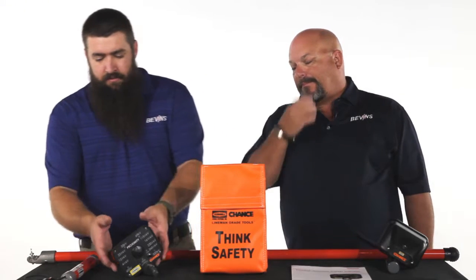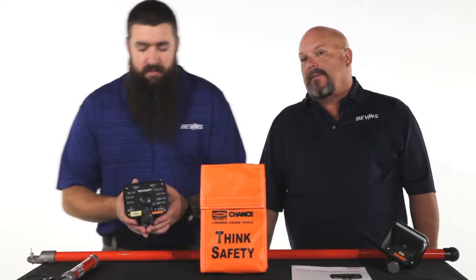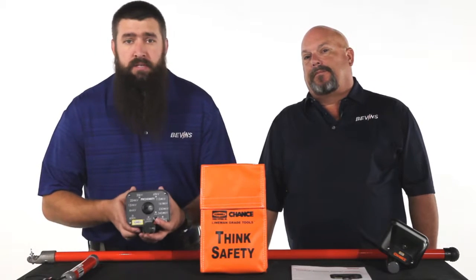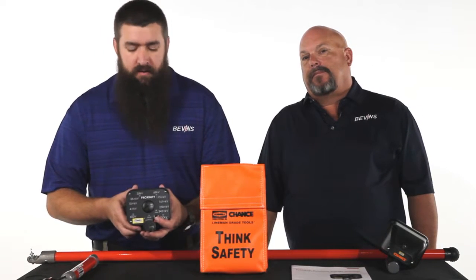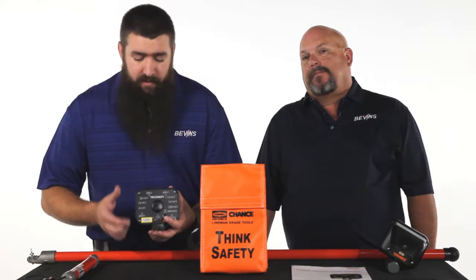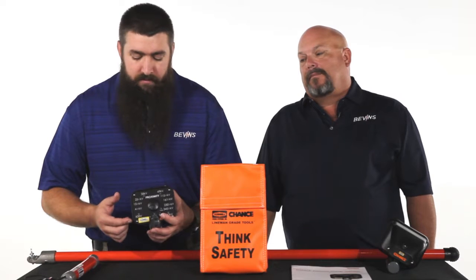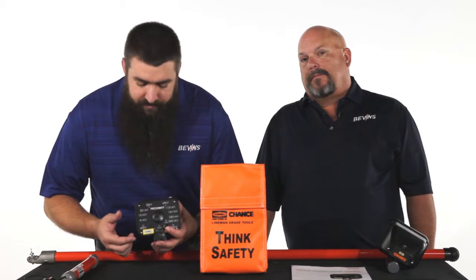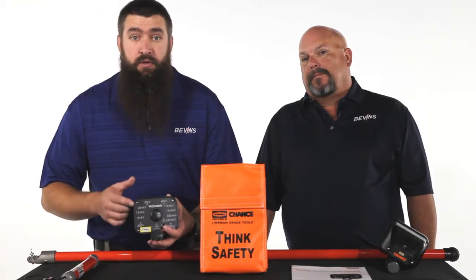Now, a unique feature that we built into the proximity tester is a user-defined range. And we're going to go through how you get to that feature. So from the off position, what we would basically need to do is press and hold the power button, just like turning it on, but we need to hold the power button down even longer. So after the initial beep of the audible alarm, we'll see the LEDs begin to illuminate slowly.